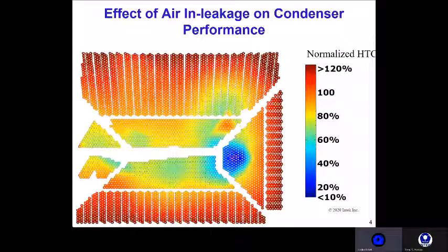This is an airbound zone, which means that these tubes are nearly shut off from steam reaching them. Intek has been able to show that this is typically the result of poor design of the condenser's air removal section. Now let's look at how this combination of a stagnant zone combined with the airbound zone behaves in the presence of an air leak.